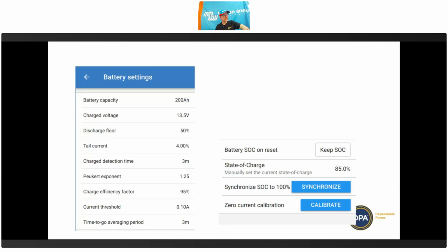So charged voltage, tail current, and charge detection time. When you set this up, you don't normally need to change these values. The default ones are usually fine. People like Power Plus have custom ones, and so you can change it to theirs. But I'd recommend not changing them. The main place that people go wrong is they change the charge voltage to the absorption voltage, and that's too high, and it means it will never get to 100%.